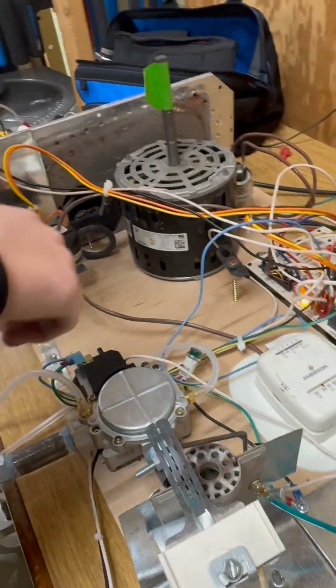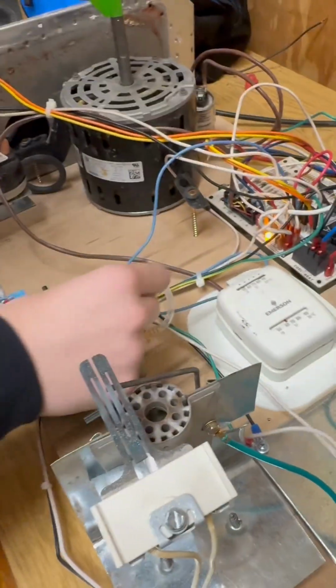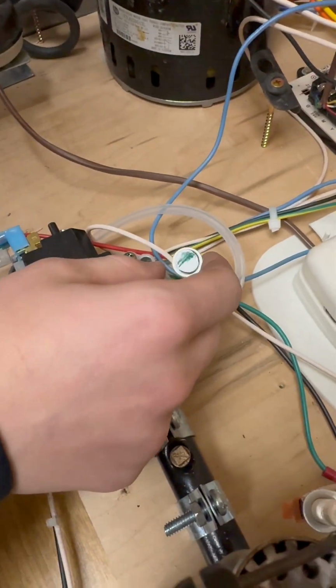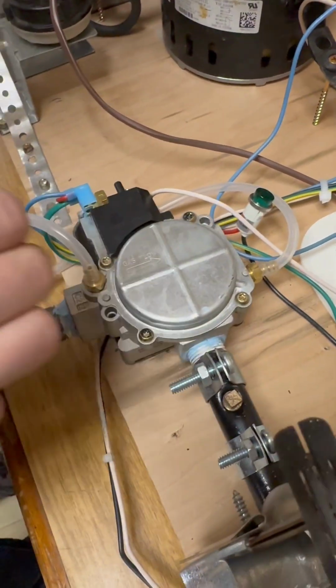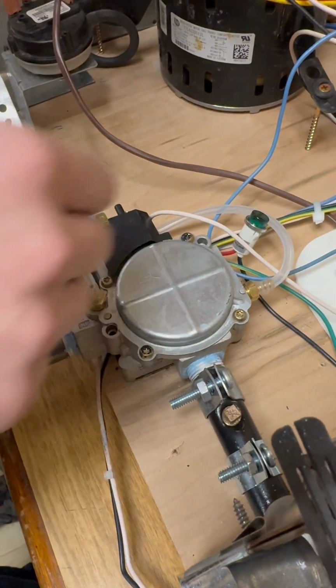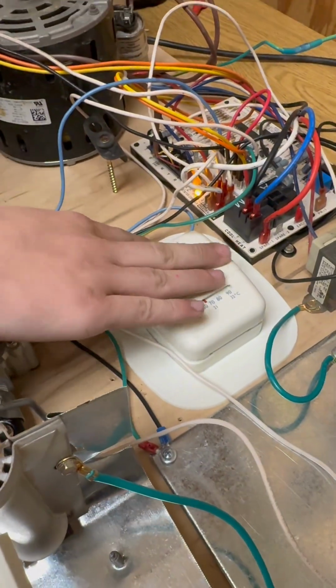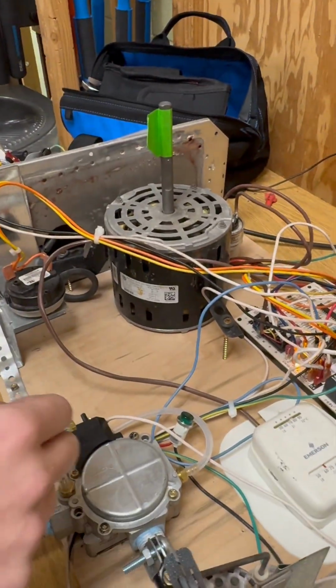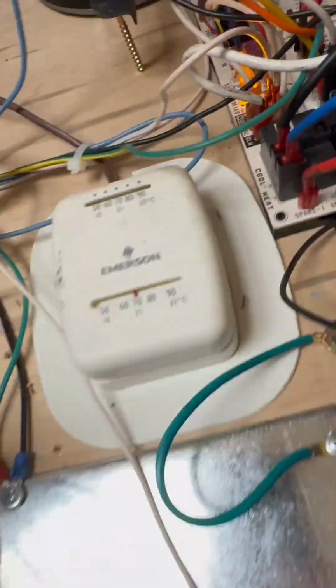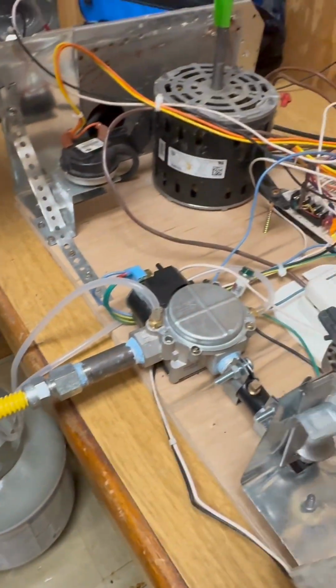So the next thing we're going to do is we have a pilot light hooked up to our gas valve to show if it's triggering or not. So we are going to run our furnace. We have our thermostat set to heat. So we're going to go through our order of operations and see if our gas valve will open.